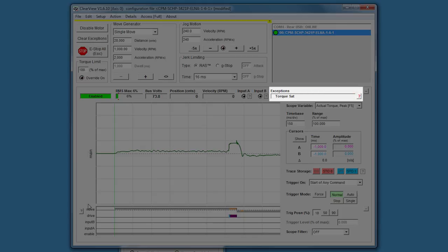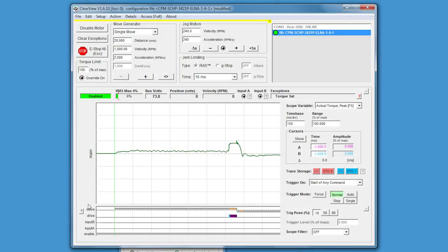During homing, we received a torque saturation signal. In this case, that's the system just telling you that homing used full allowable torque during the process, which is typical for hard stop homing, so there's no issue. Now the motor is homed and we can start the demo.